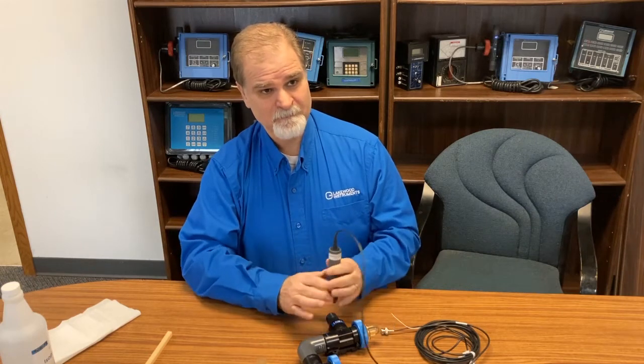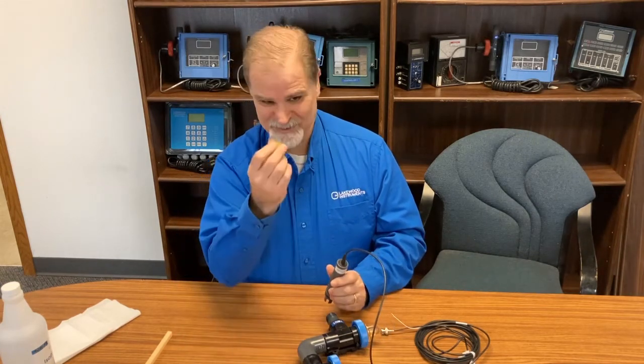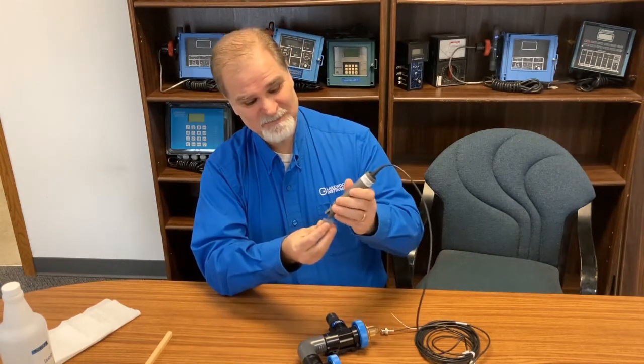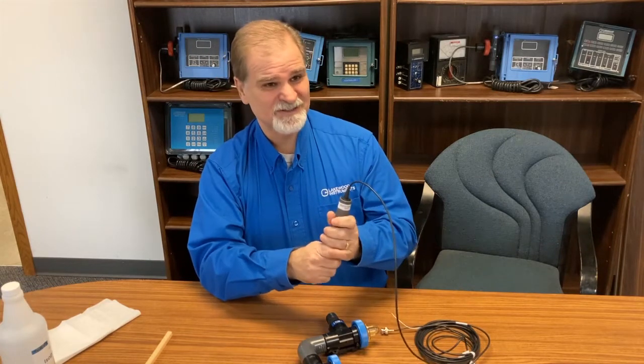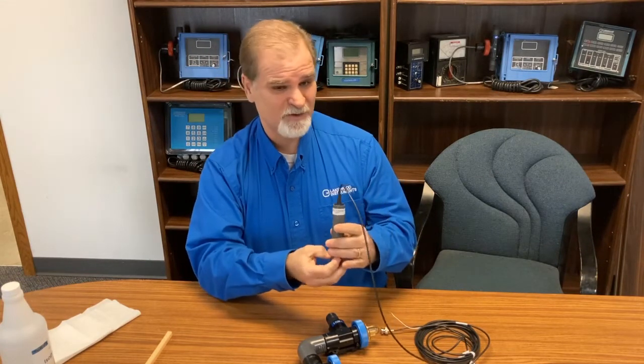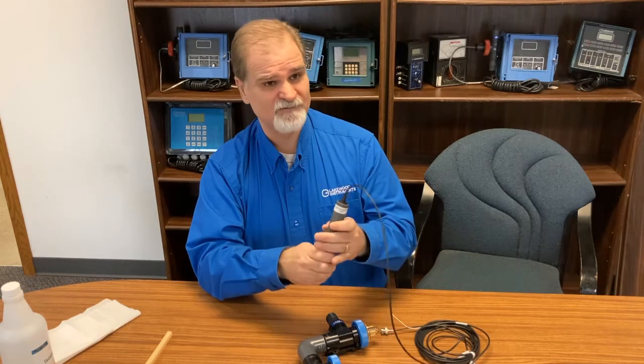And maybe put a cap on the end of the sensor so it stays wet. Always, it's shipped with a cap. You should always keep that sensor wet. You should always use electrode storage solution, or if you don't have that, you can use a pH 4 buffer solution.